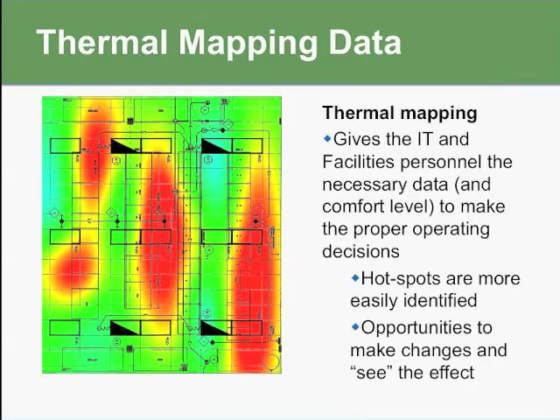And what you really care about is the inlet to the IT equipment. Okay, and that's where we've got all these temperature sensors, because that's what you really care about. The hot aisle can get as hot as it needs to get. It really doesn't affect the performance of the IT equipment. What you've got to do is keep the inlet nice and cool, but not too cool.